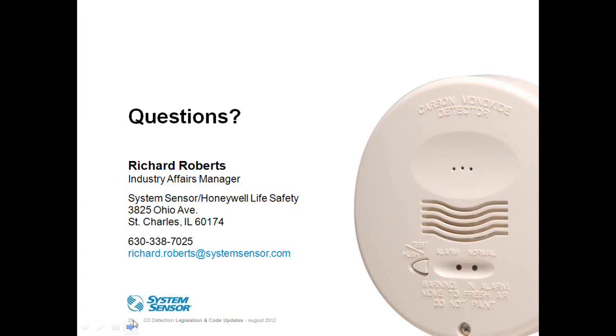Next question, Richard, a little involved here, but they're saying that the fire marshal didn't like CO detectors on the fire alarm system because of frequent false alarms, and he was under the impression that CO detectors went off at 30 parts per million. And he said, listening to your descriptions, I'm wondering if this was a very old system, and were past codes in fact set at 30 parts per million? As I addressed in today's presentation, the early UL 2034 alarm thresholds were different than what the current ones are. And I think I said that they were changed in 1998.